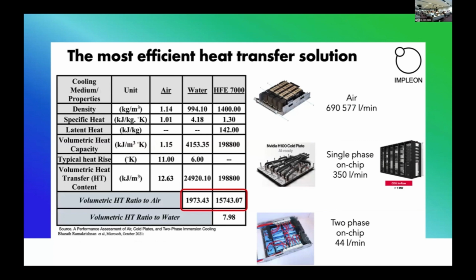Another thing which I want to deliver to you: when you get the server, make sure that the cooling solution is the best which you can use. So if you have a GPU server with heat sinks, it will need, let's say, 700,000 liters per minute to cool them down. If you use on-chip cooling with water, you will need around 350 liters per minute per rack. But if you look at the properties of two-phase, you will see that the difference of the flow rate between water and refrigerant is 8 times. So an AI rack with two-phase will need 44 liters per minute instead of 350. This flow rate, 350 liters per minute, creates conditions where you are not able to put a CDU in the rack and you need a row level CDU to provide this flow rate per each rack.